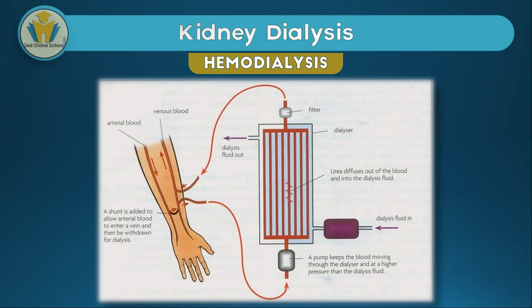At the other end of the dialyzer, we've got a filter which ensures there are no other particles entering the blood. At the right and left part, we've got one side where the dialysis fluid is coming in and the other where the dialysis fluid is going out. You should note that the blood usually will have a higher concentration of urea, water, and salts. Therefore, these unwanted substances will flow down a concentration gradient into the dialysis fluid. Therefore, you should note that the dialysis fluid must have the same glucose concentration.